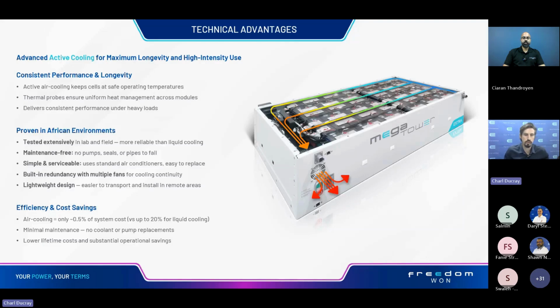Cool. Then speaking about the cooling of the megaTower, each megaTower battery module has active air cooling per module. Essentially, this ensures that your cells are kept at a safe operating temperature at all times. We've got multiple thermal probes throughout each battery module, so you can see exactly what the temperatures are per module, not just the full megaTower. And essentially what that does is ensure that we can deliver consistent performance under heavy loads and that the cells don't overheat.